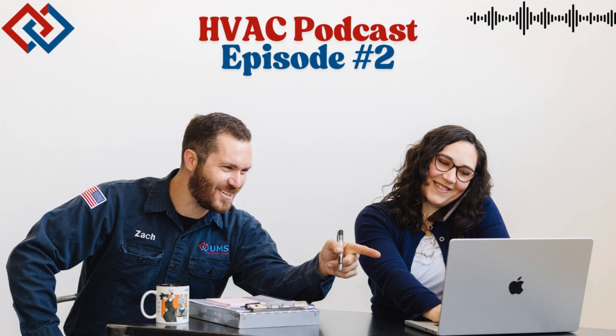Gotcha. And what about makeup air units? I don't think I've ever encountered that term in a residential context. What are they and what do they do? Makeup air units, or MAUs, are often essential components of commercial HVAC systems, particularly in buildings with significant exhaust requirements, think restaurants with kitchen hoods, industrial facilities, hospitals, labs. Places exhausting a lot of air. Right. These units are designed to draw in fresh outside air, filter it, and sometimes condition it, heat or cool it slightly, to replace the air being exhausted from the building.